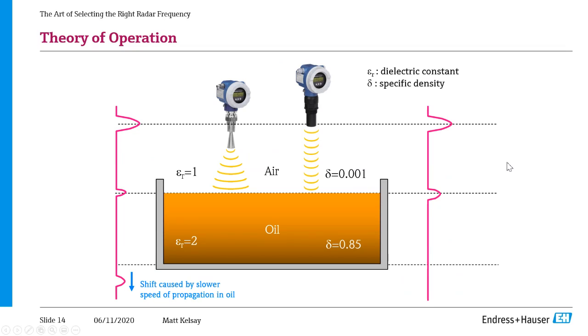Next, you look at an ultrasonic in the same application, and this one actually looks very similar to what it does in water. And again, that's because we're looking at a difference in density, which air and oil still have a plenty big density difference, that all of that signal is reflected back up to the unit. It becomes very easy to measure.